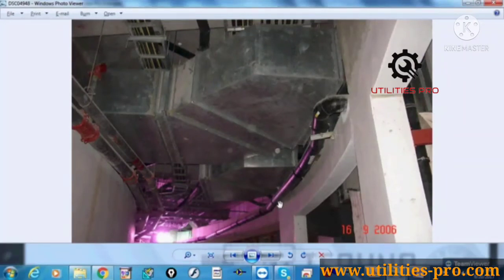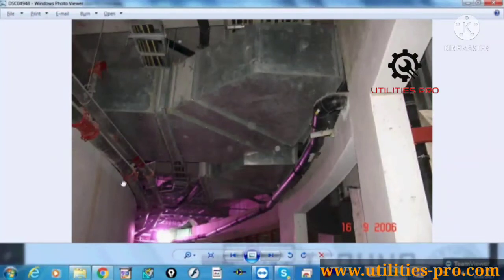Plumbing also will be used on a daily basis, but firefighting will be used only in case of a fire event. Till that time, proper maintenance is required. And for easy maintenance, if this pipe is just above the false ceiling, it will be easy to access. So for that reason also, it is recommended to run this firefighting pipe below the duct or just above the false ceiling.